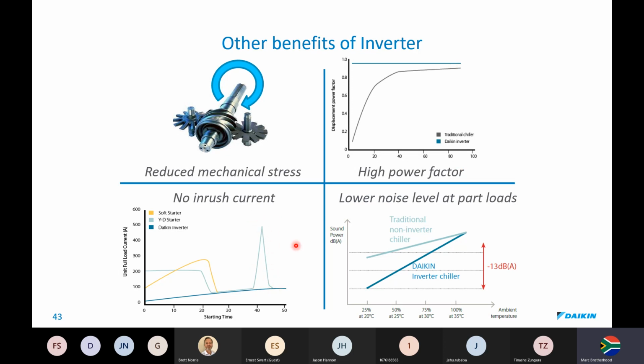When you have inrush current, a switch gear takes a lot of thermal load on it, and your breakers and your contactors don't last with huge inrush currents. And even your cables heat up terribly. We don't have inrush current. It's just a linear current draw, which is the bottom.